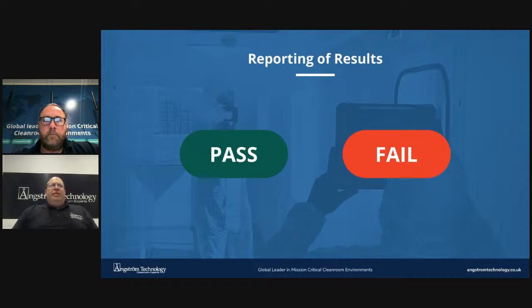It is also recommended that the estates or maintenance team within the client's facility hold critical spare parts so that the downtime is reduced to a minimum. At Angstrom Technology, for some clients that have already acquired their specific critical spares, we will hold them within our warehouse area, and these are brought to site when the qualification takes place for a time-sensitive replacement.